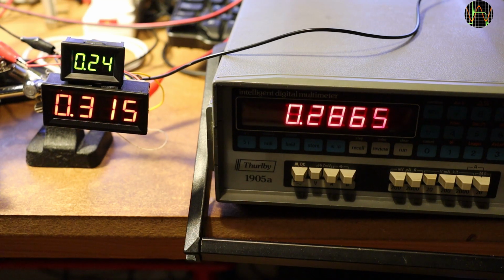They are quite a bit off at low voltages, and the 4-digit one did not even show anything until at least 0.25 volts has been exceeded. When scaled to the monitor output, that means voltages below 150 volts are shown as 0, which is unacceptable to me. Raising the voltage further shows that it takes about 1.5 volts, which would be the equivalent of 900 volts, before the accuracy of the lower 4-digit meter approaches acceptable values, while the upper 3-digit meter only really gets going from 4 volts or equivalent 2400 volts onwards.